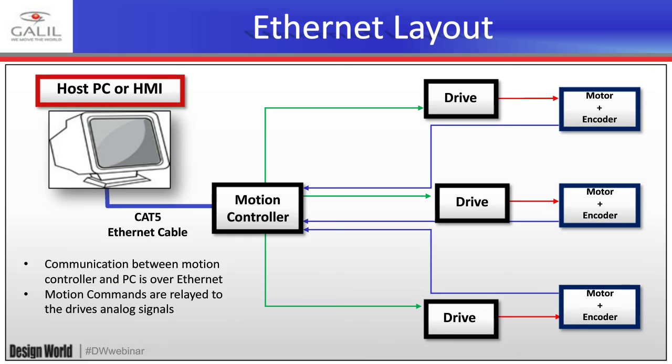In contrast, here's an Ethernet layout: a host PC or HMI in the control center communicates with a motion controller over CAT5. The motion controller then communicates with the drives via analog control reference voltage, or step and direction if it's a stepper, and relays that information back to the PC. The deterministic real-time motion is handled on the motion controller, as opposed to the PC — specifically because Ethernet communication is not deterministic, unlike EtherCAT.